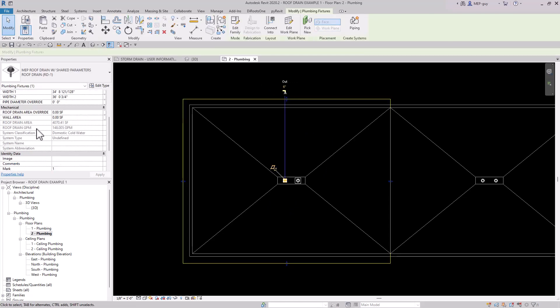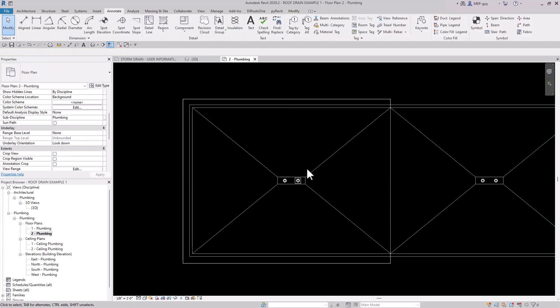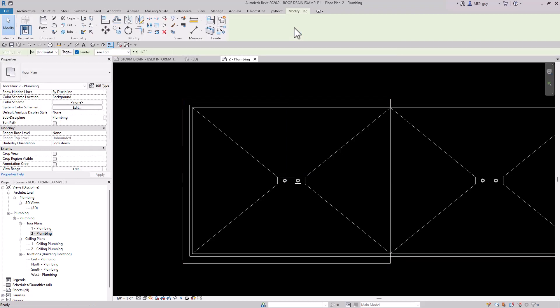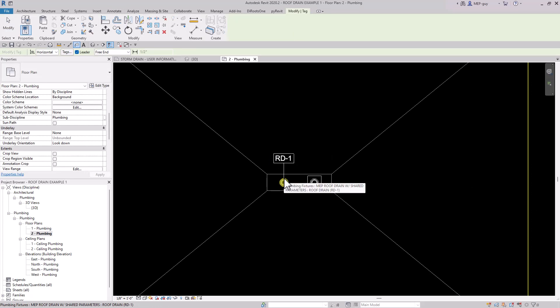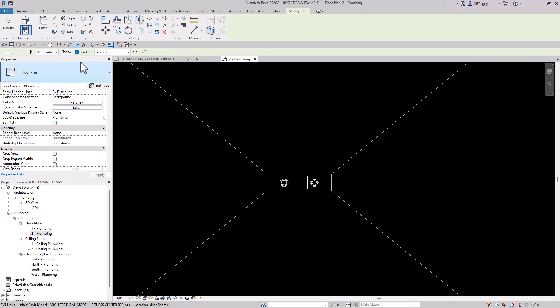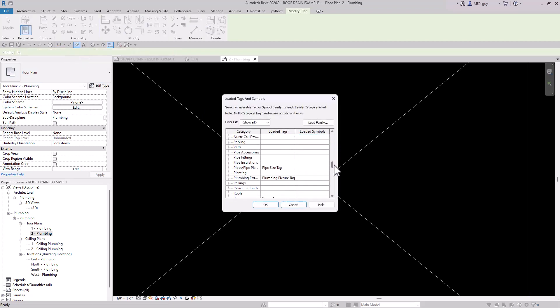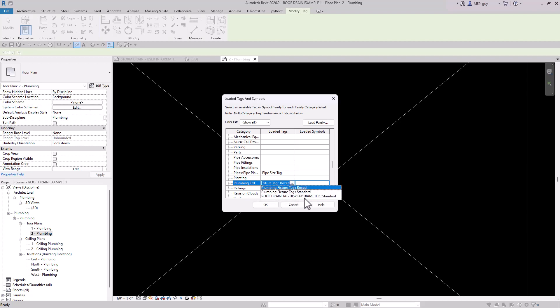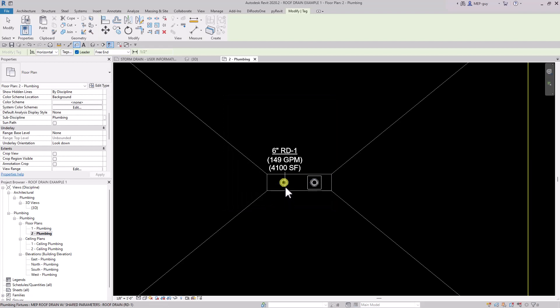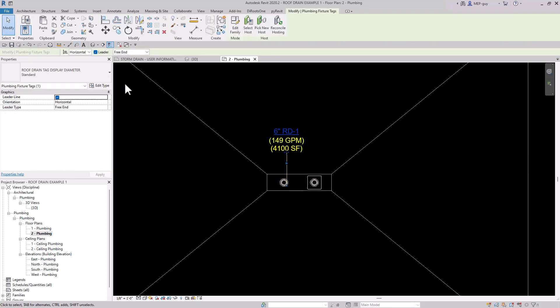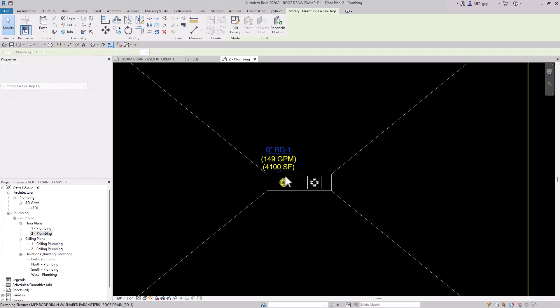Clicking the roof drain shows the roof drain area is now 4,070 square feet. I'll round up to 4,100 — going to Roof Drain Override and typing 4100, which shows the GPM as 149 GPM. Now I'll tag the roof drain: go to Annotate > Tag by Category. The GPM info wasn't showing because the wrong tag was loaded, so I'll click Tags, go to Plumbing Fixtures, and select the Roof Drain Tag Display Diameter. Now the roof drain is tagged correctly. I'll remove the leader by unchecking that box.